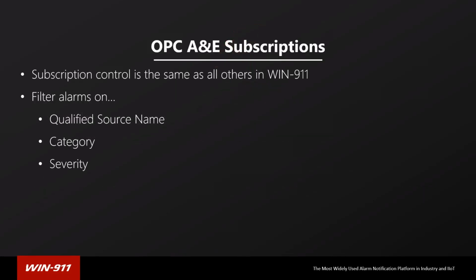And subscriptions, I'll just run through this real quick. The way it works is you connect to a server, and then you subscribe to, or you filter alarms based on a few different criteria. So for A&E, you're filtering on the source name, which is like the tag name. It is the tag name or alarm name.